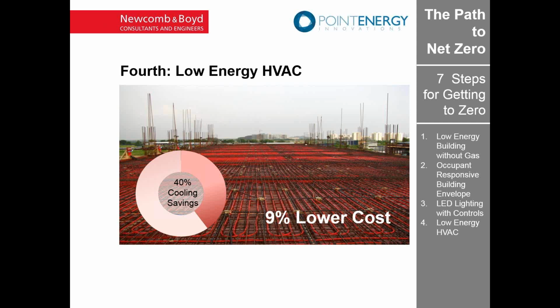In this particular case, I wrote an article about it on my website, ASHRAE Journal, where he took a 250,000 square foot building and cut it in half: one half with radiant, one half with optimized VAV. It was metered very accurately and in detail. The radiant side used 40% less energy than the VAV side, with the same solar load and lighting, and it cost 9% less to build. So it's a cost-effective solution.